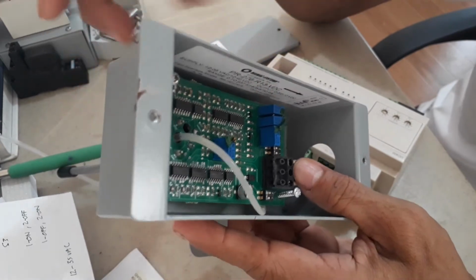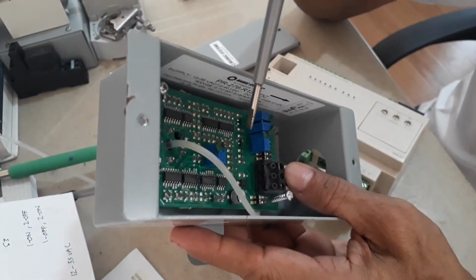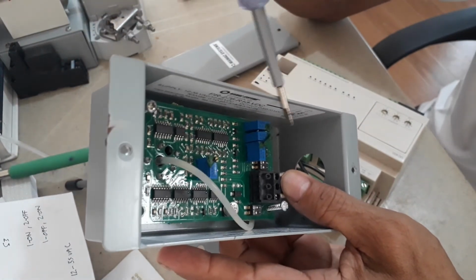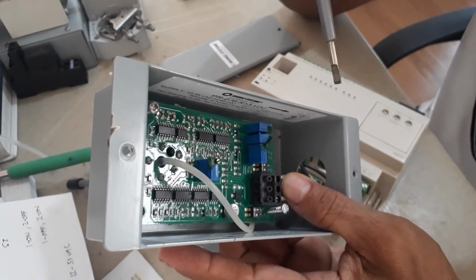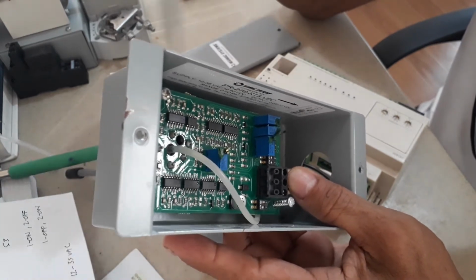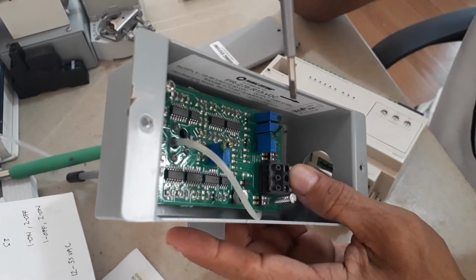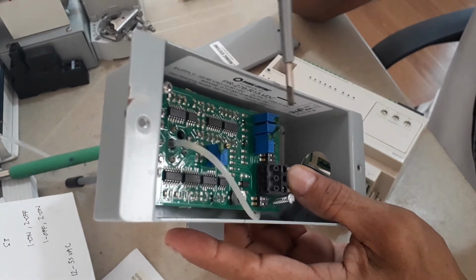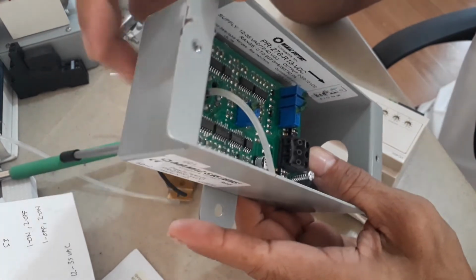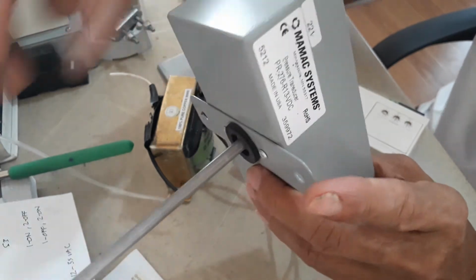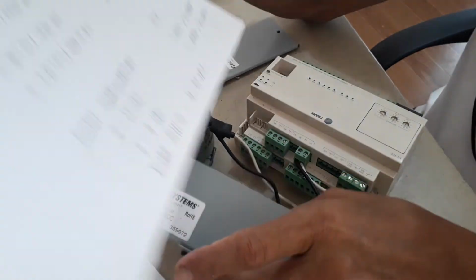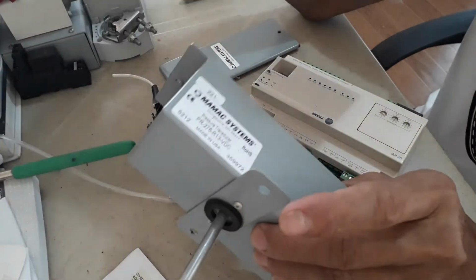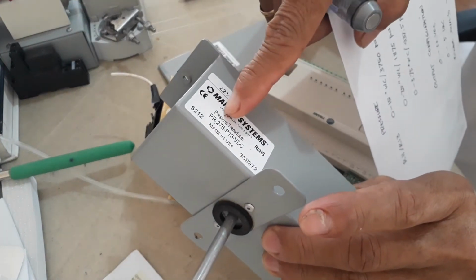Now here, there are several configurations that you can make. Now first, the output, you can set it to 0 to 5 volts or 0 to 10 volts. Now I set it to 0 to 10 volts. This is the factory setting. Now the pressure range, okay, the pressure range. Now let me show you the pressure range of this. The pressure range, as the model dictates, PR276R13, okay. Now volt DC, the output is volt DC.